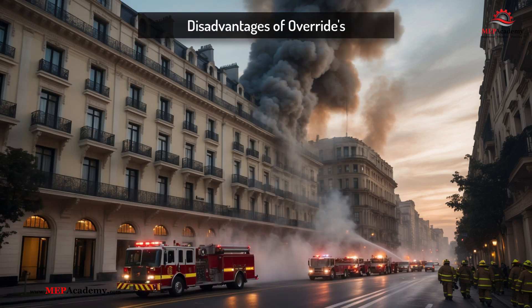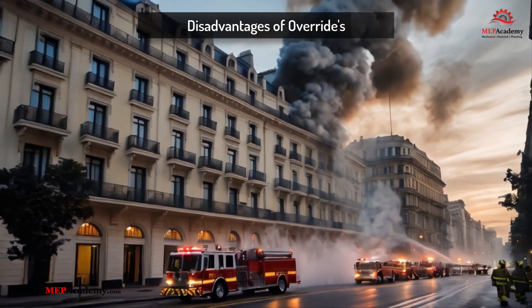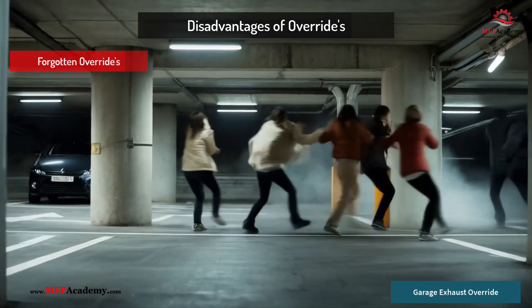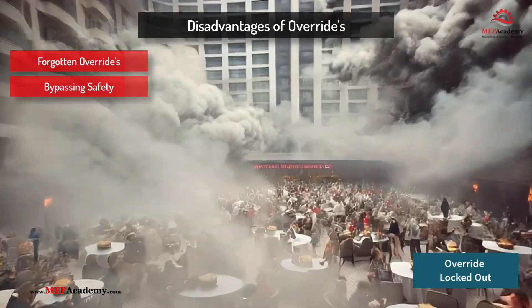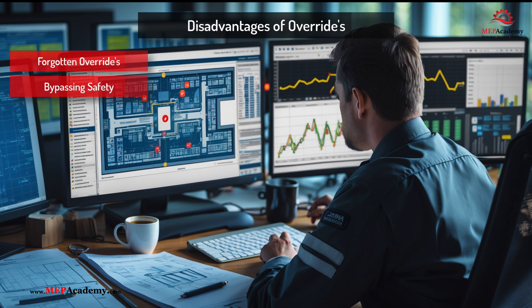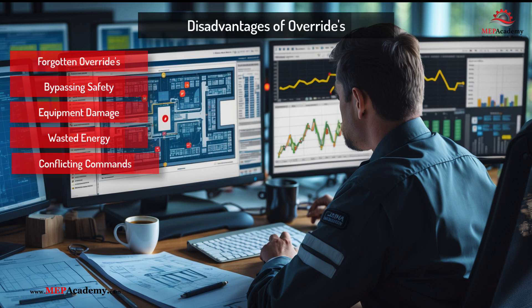Disadvantages and risks of overrides: Despite their usefulness, improper use of overrides can lead to serious operational problems. Forgotten overrides can cause unintended consequences such as frozen coils or overheating. Bypassing safety mechanisms such as overriding alarms, safeties, or critical sensors can introduce safety hazards like turning off smoke evacuation fans. Equipment damage occurs when forcing equipment on or off outside of its normal operation sequence, leading to mechanical failure or excessive wear. Energy waste and inefficiency result when overrides prevent normal energy-saving automation, increasing operating costs. Conflicting commands from multiple overrides applied to interconnected systems can cause operational conflicts.